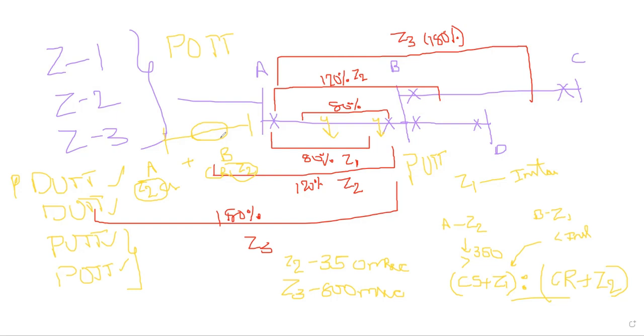So this is zone 2. Always zone 1, zone 2, zone 3. And zone 4 is the reverse direction. If zone 1 picks up, we send a signal to the other end of the breaker through some communication, saying that I am seeing a fault in zone 1. If it is seeing a fault in zone 2 and it receives the carrier, it will also trip. So this is the main scheme. Generally, we will see that, and come to the POTT scheme.